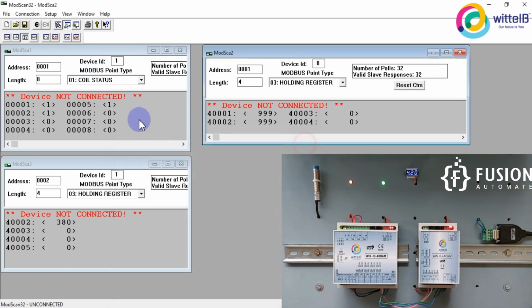You can see in this window, this has slave ID 1, or you can say device ID 1, here device ID 1. So these two windows are associated with this Modbus IO card, and here you can see device ID 8. This window is associated with this other Modbus IO card. I hope that is clear to you.